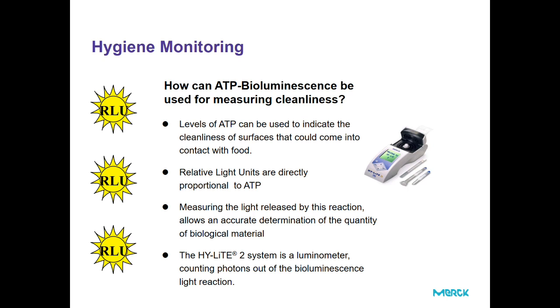Levels of ATP can be used to indicate the cleanliness of surfaces that could come into contact with food, which we define as critical control points. The relative light units measured by the luminometer are proportional to the amount of ATP. Measuring the light released by the reaction allows us to accurately determine the quantity of biological material. The HY-LiTE 2 is a luminometer which counts the photons coming from the bioluminescence light reaction and gives us the value of the ATP present in the sample.